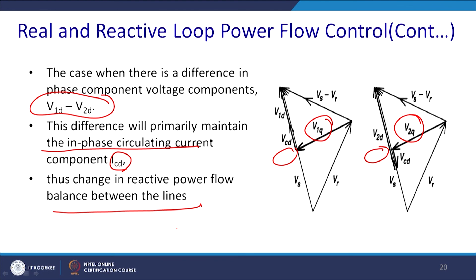We actually come to this point then. In the general case, a difference may exist in both the in phase and the quadrature voltage components, which will maintain the circulating currents, changing both the real and the reactive power flow balance between the lines. This distribution of the real power flow over the interconnection forming the loop circuits can be controlled by the PAR. The phase angle regulator injects a quadrature voltage in series, thus it can effectively control the VQ in series with the circuit loop, resulting in the flow of the in phase circulating current. So, it will increase ID1 and ID2.